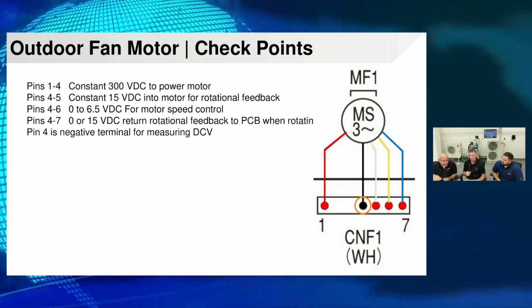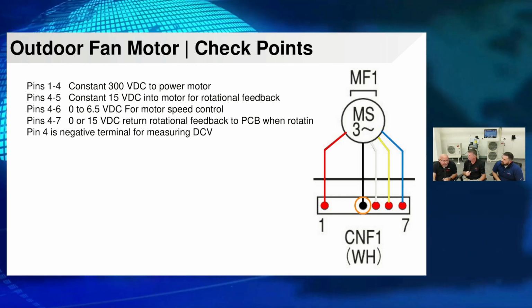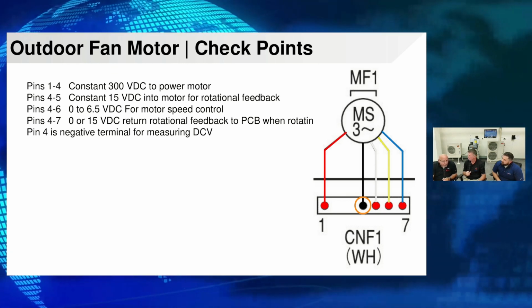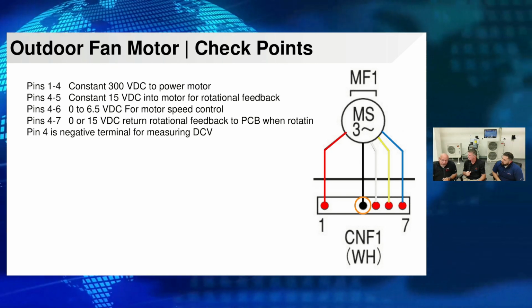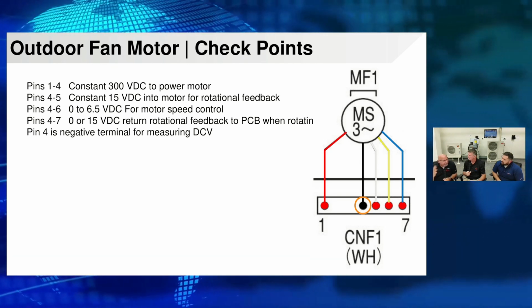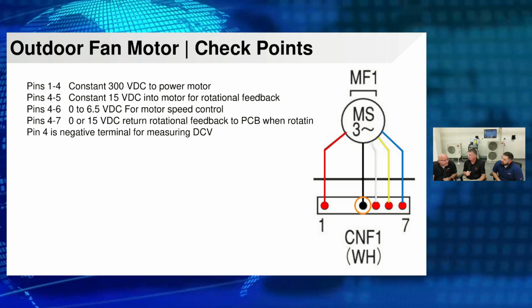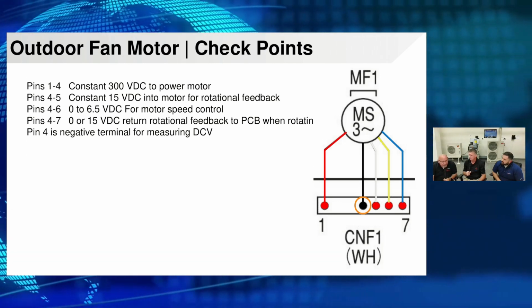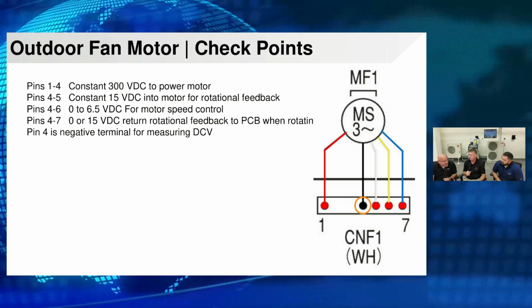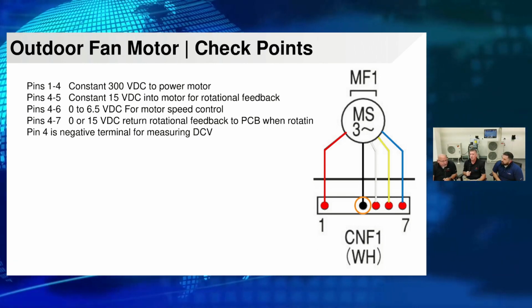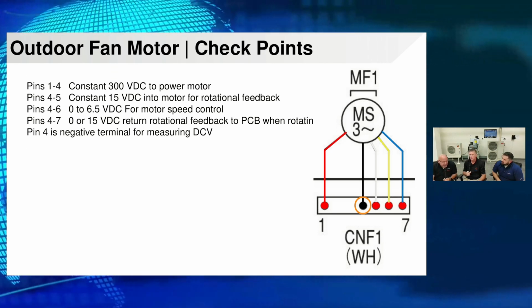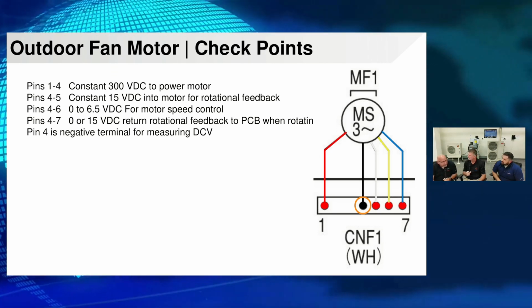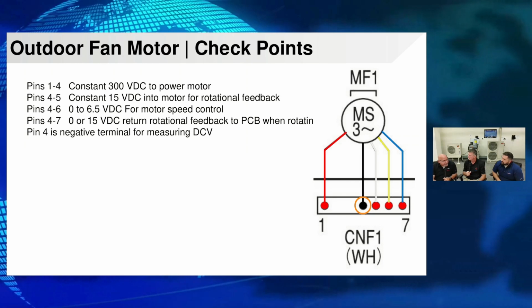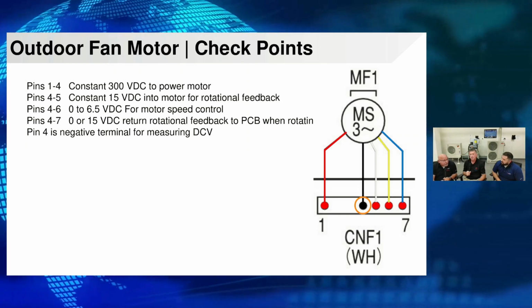Again, that's a rotational feedback being sent from the motor back to the board so it knows how fast it's running. It's a deflection - 0, 15, 0, 15, 0, 15. Most meters will not see that signal because the motor runs so fast. Some meters will be able to display 7.5 volts DC, which is the average.